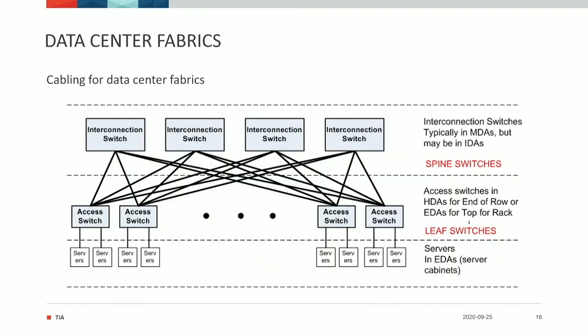We have an addendum in the data center standard regarding how to design telecom cabling infrastructure for data center fabrics. This leaf-spine architecture, which is now very common, was originally considered to be challenging for data center infrastructure standards. One switch manufacturer mentioned to the director of standards in TIA that he didn't think TIA-942 would apply to data center fabrics, so we took that on as a challenge and developed an addendum for how you support data center fabrics using structured cabling, including fully meshed and leaf-spine architecture designs.